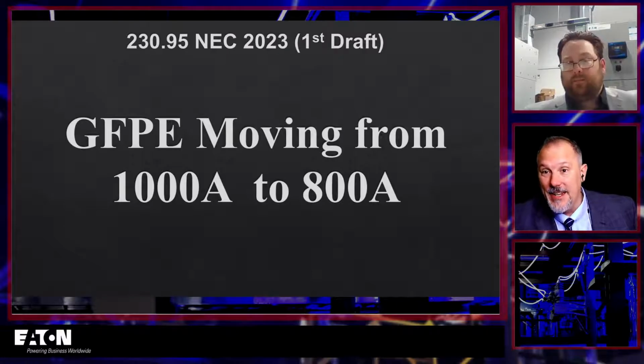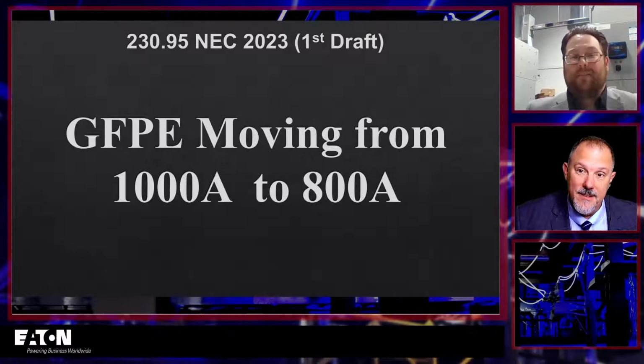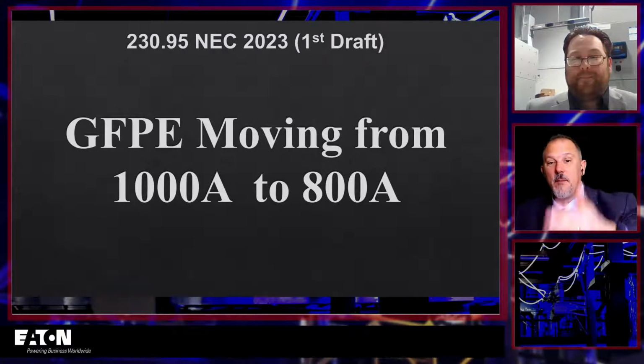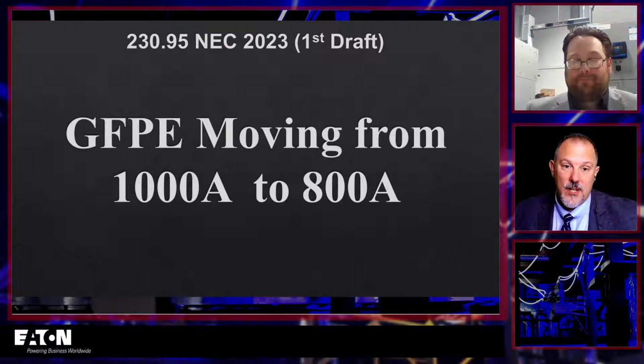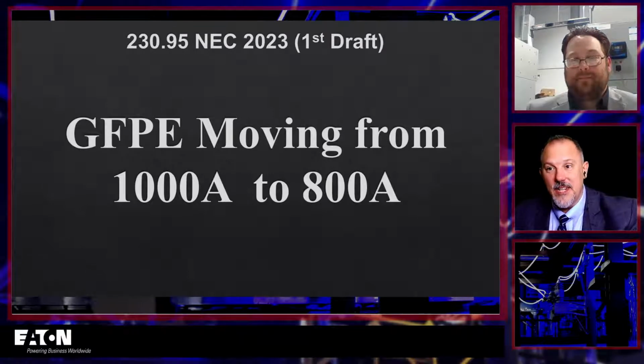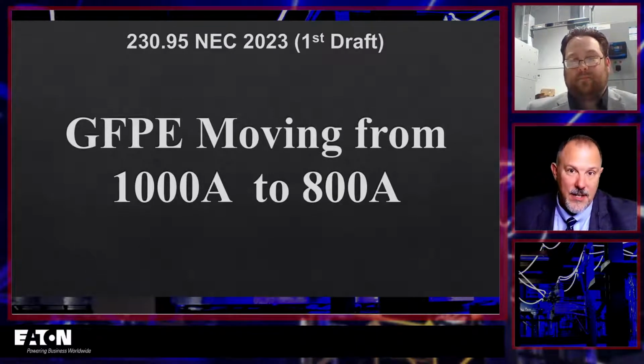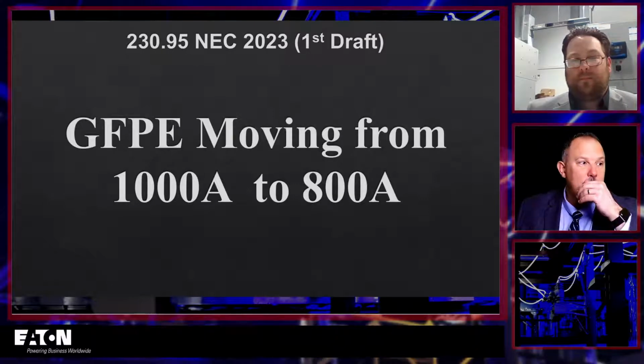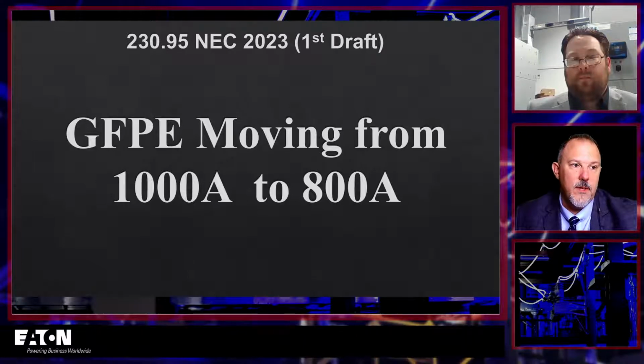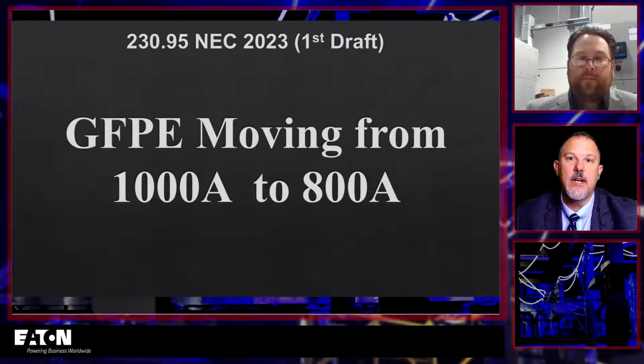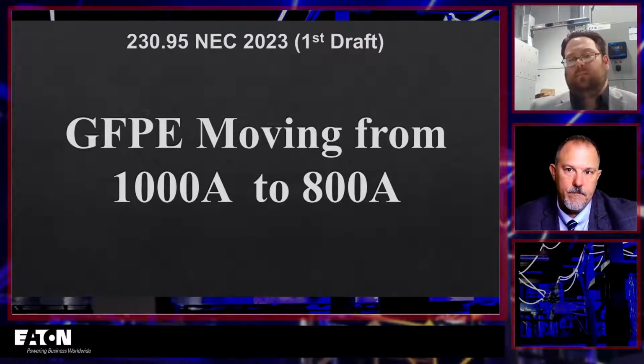Because what we're doing with that, the 2023 code is looking at taking 1200 amps and moving it down to 1,000. Yeah. So you've got GFPE moving from 1,000 to 800 for the 2023 code cycle. You've got arc reduction technologies going from 1,200 down to 1,000 amps. So there's a reality that technically it's not about the size of the service. It's about the clearing time of the overcurrent protective device with respect to the currents that are flowing, whether it be a ground fault current or an arcing current.